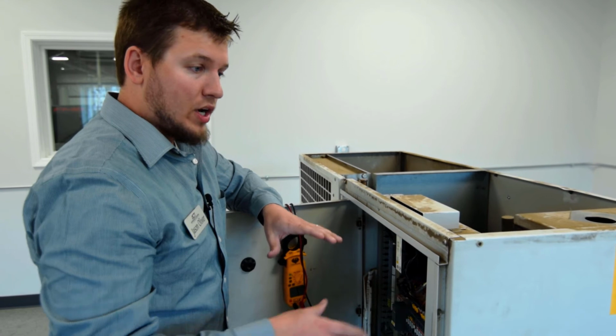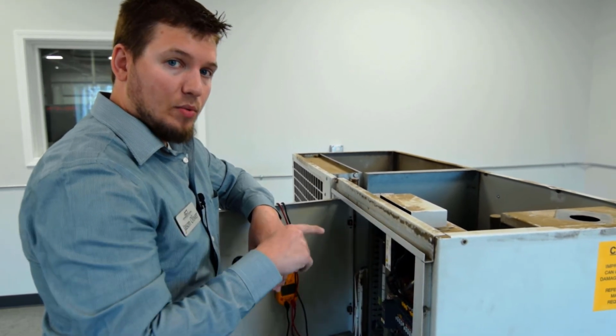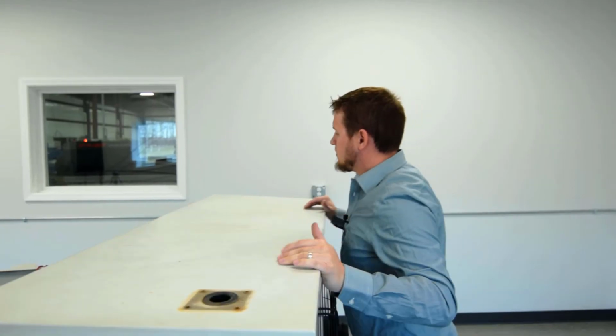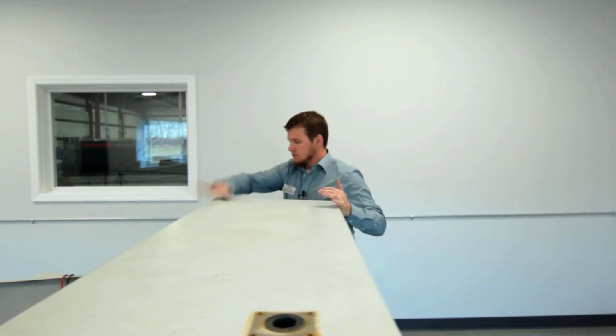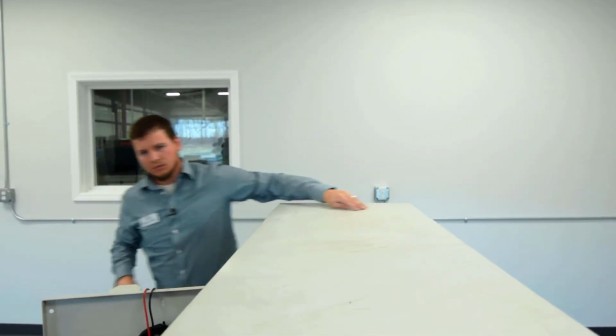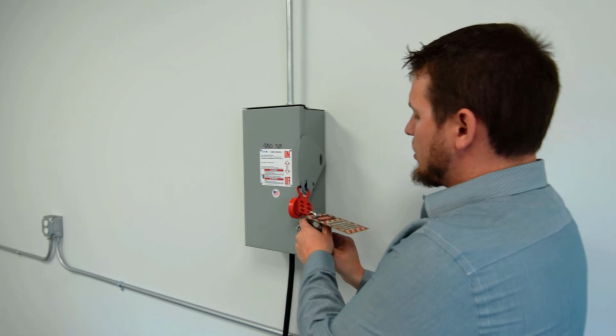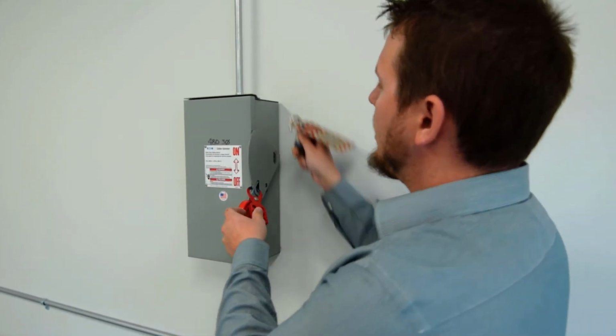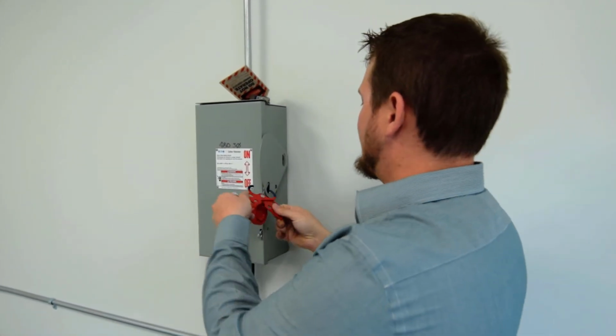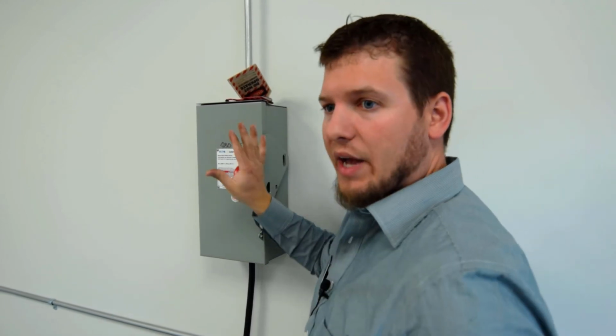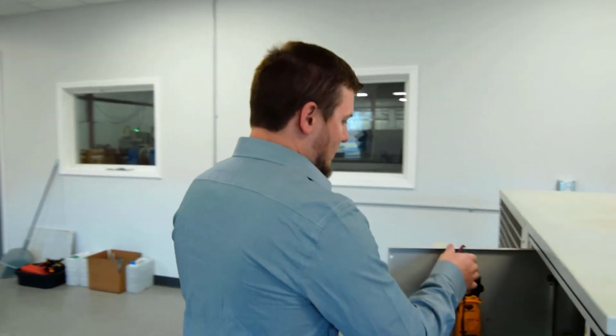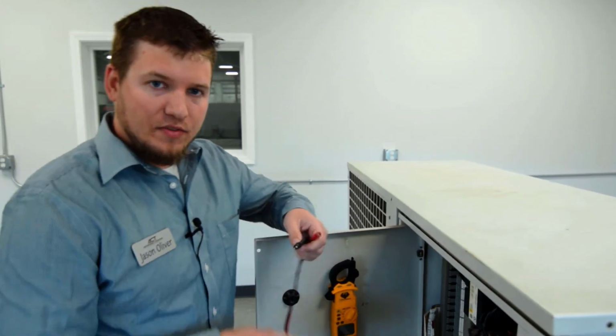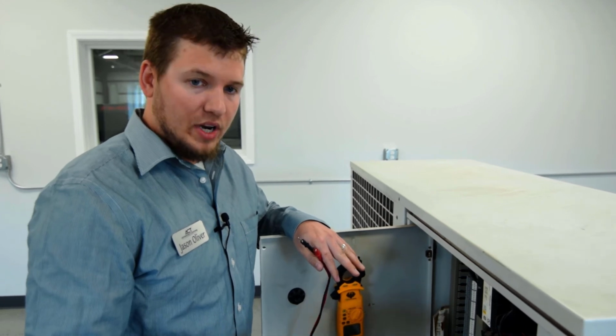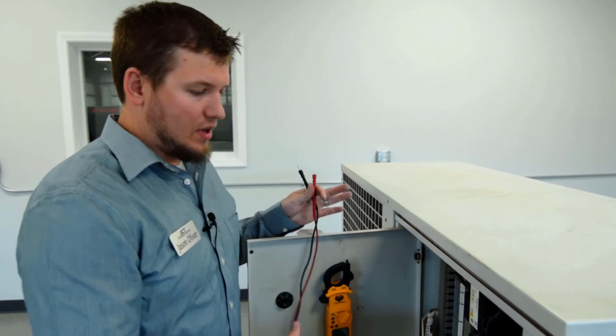At this point, we're going to have to put the cover back on and turn the power back on. So let's do that now. Once you got the cover back on, you can then, and it's safe to do so, go ahead and remove your lockout tagout system and turn the power to the chiller back on. At this point, you're going to want to use caution while working around these electrical components. We're not going to, for this video, turn on the chiller, but at this point the chiller would be up and running and it'd be loud.